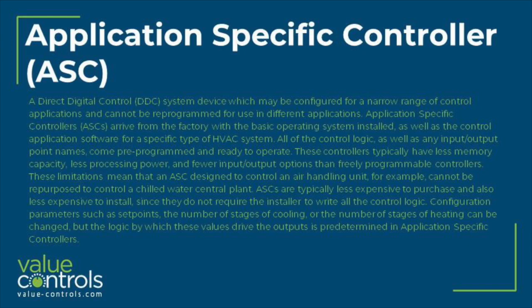Application-Specific Controller, or ASC, is a direct digital control, or DDC, system device which may be configured for a narrow range of control applications and cannot be reprogrammed for use in different applications. ASCs arrive from the factory with the basic operating system installed, as well as the control application software for a specific type of HVAC system.